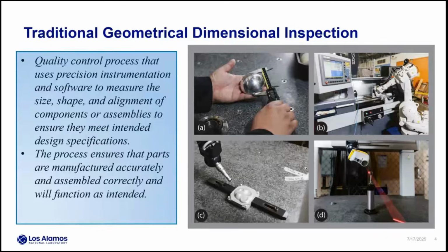And then we have what is referred to as a coordinate measuring machine. This is used to do detailed inspection of a component after it's been fabricated, or maybe during a stage of its fabrication it's pulled off the machine. And what you see in item C there is a touch probe, a high precision device that's going in to basically touch the surface and record a single point on that surface with high precision, high accuracy.